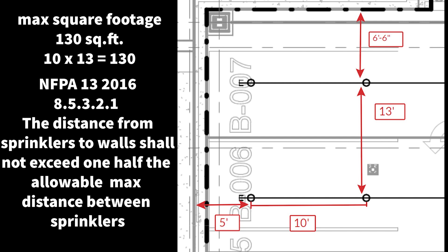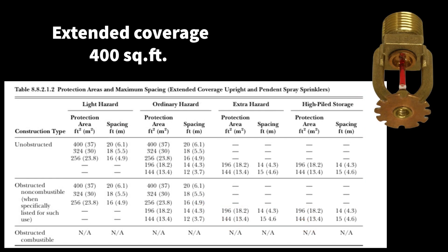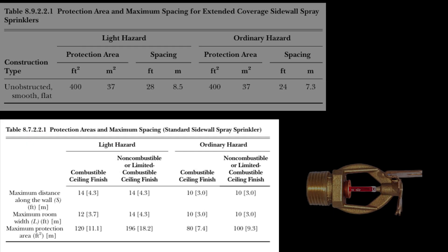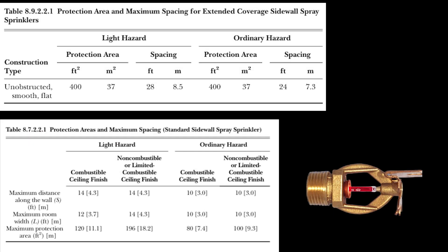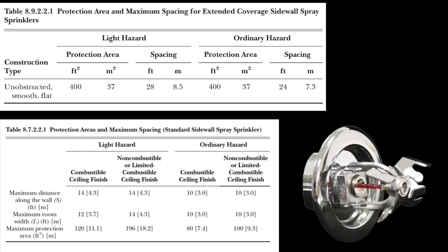So depending on the direction of the spacing, in the distance going 10 feet we can't be any more than five feet off the wall, and in the distance going 13 feet we can't be any more than six foot six off the wall. Other tables include the extended coverage upright pendant, the standard spray sidewall, and the extended coverage sidewall.